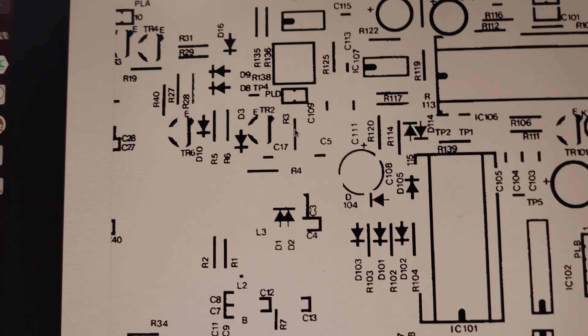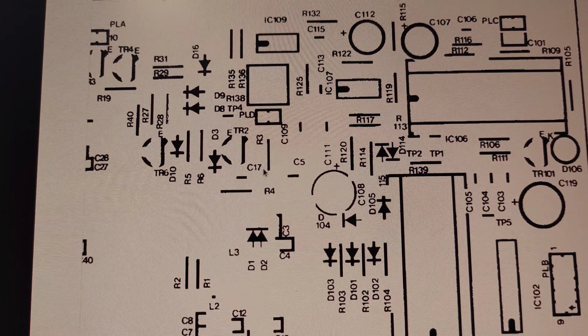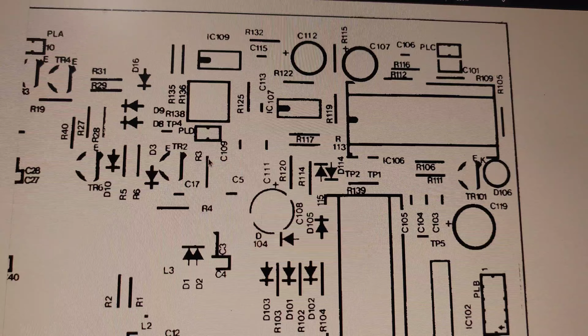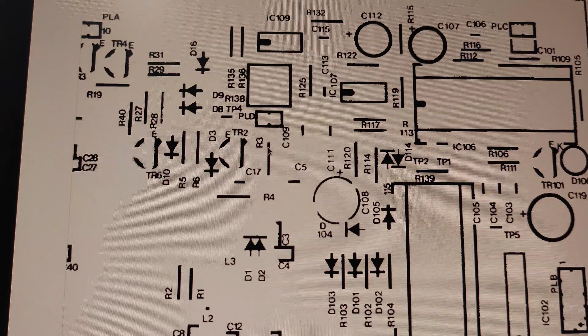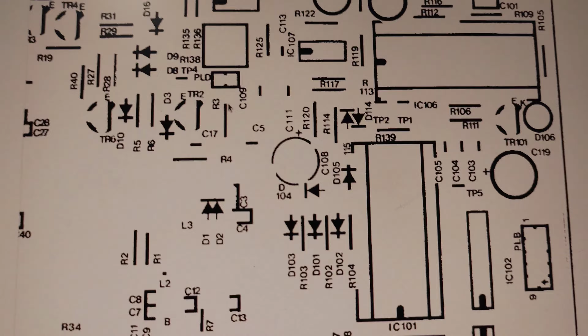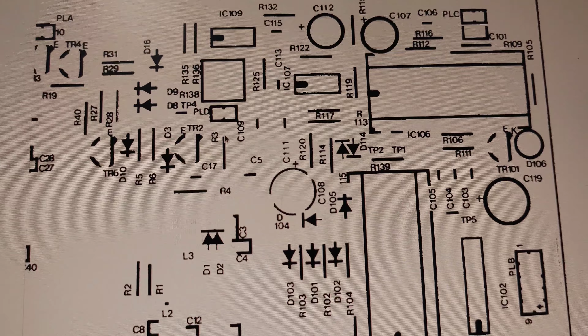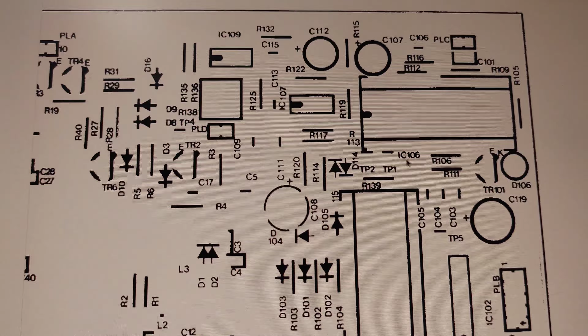So if you lift this PLD jumper, it actually opens up the PLL feedback, and whatever voltage you apply across this resistor R3 is actually the VCO control voltage. So here's where I found something really interesting. When following the instructions and applying 3 volts to R3, I was able to get the correct frequency to output on my spectrum analyzer out of the generator output, 165 megahertz, which is exactly what the service manual called for. That indicated to me right away that there was something wrong with this control voltage, and that's why the PLL wasn't locking, because the VCO was just going to the wrong frequency.